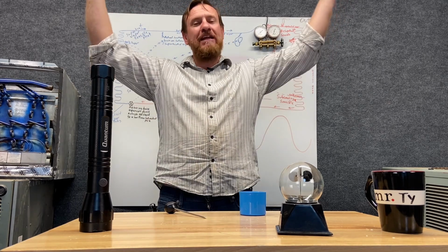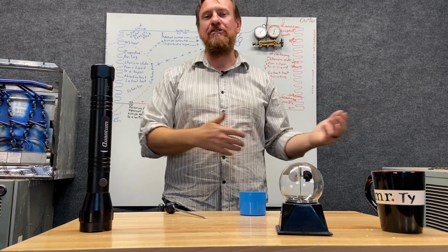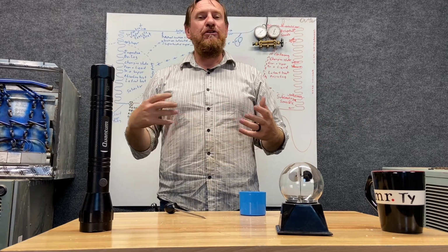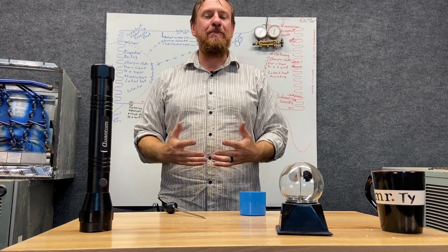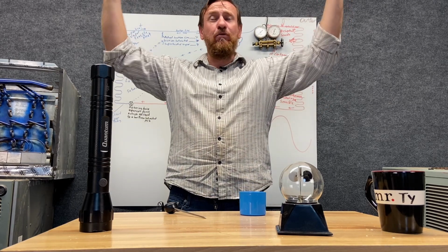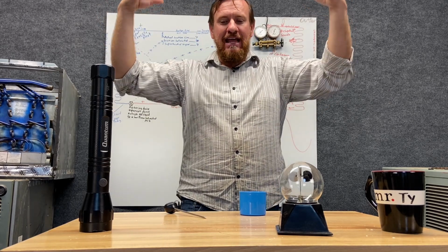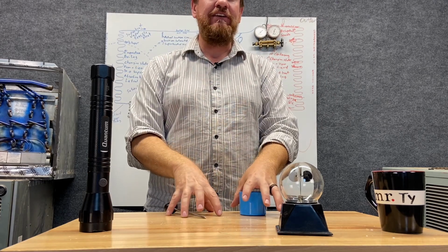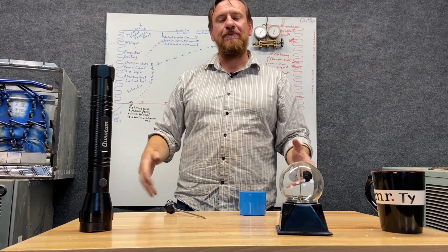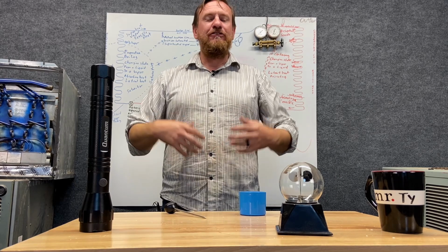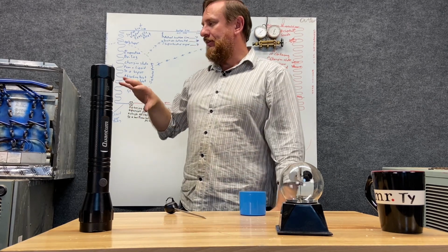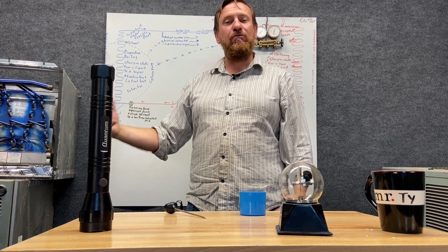Mechanics. You have a huge mechanic shop, the doors are open, trucks are coming in, trucks are coming out, etc. Well, you can't afford to heat that whole entire space. But if you use radiant heat, or even in workstations where you have radiant heat coming down, that's heating the people and the objects instead of heating all of the air. It's a very effective way of heating. So radiant heat's important. Now, when we deal with evaporative coolers and heaters, there's a radiant heat effect.